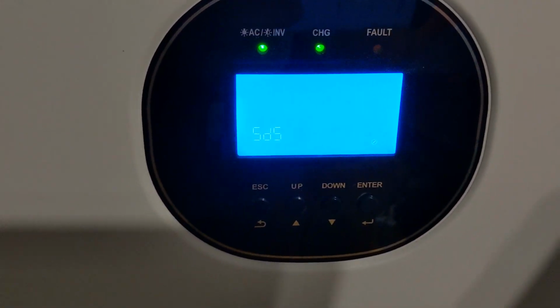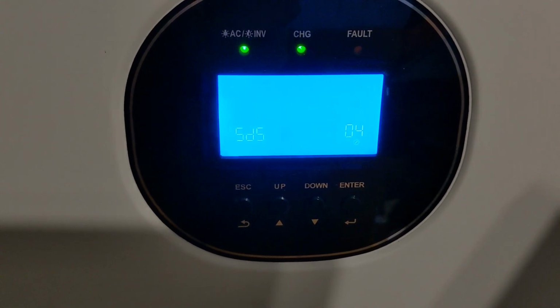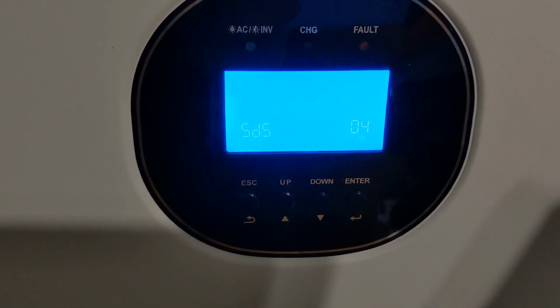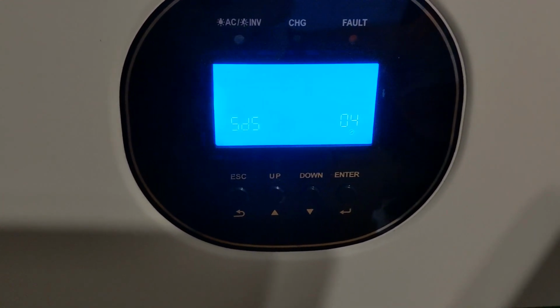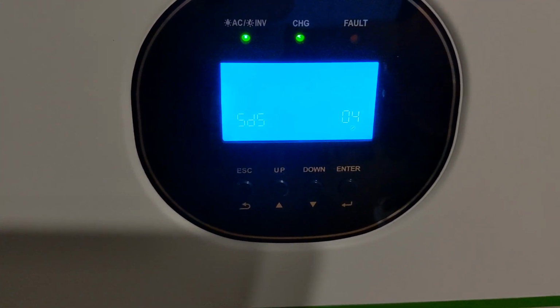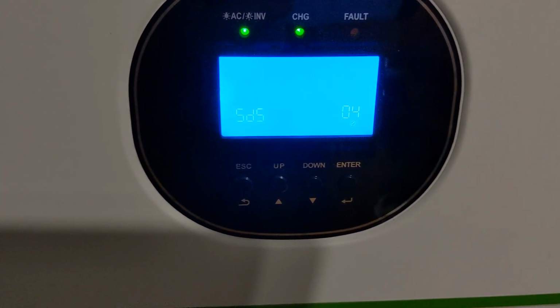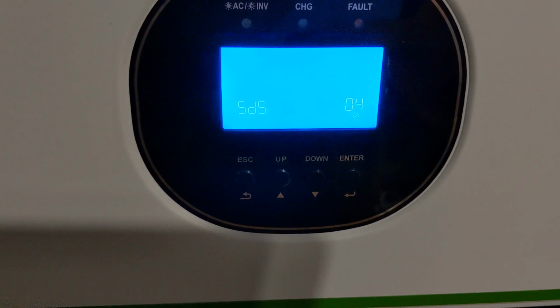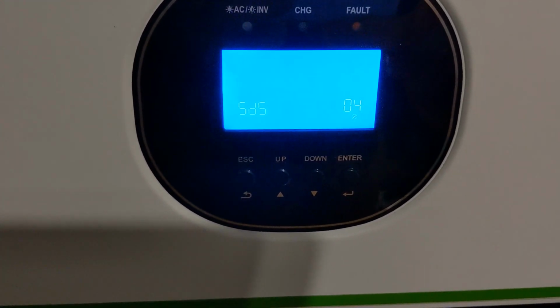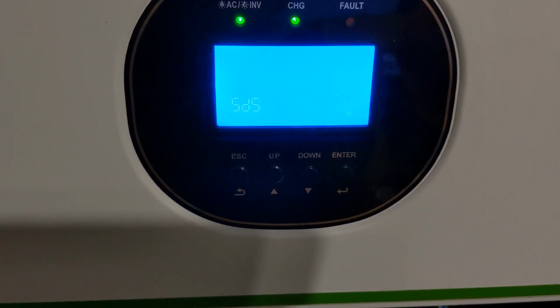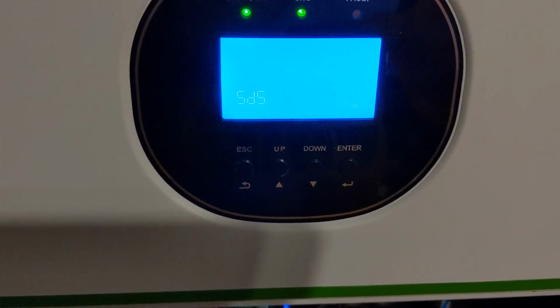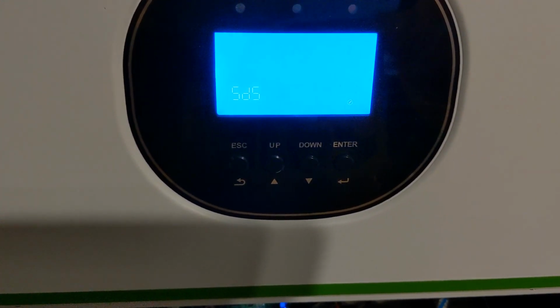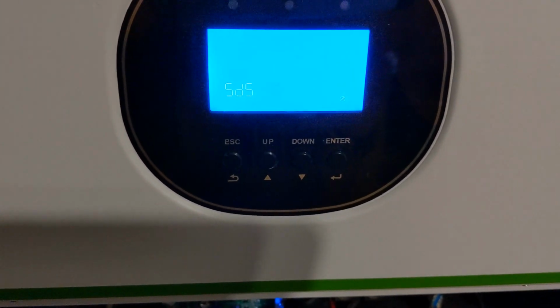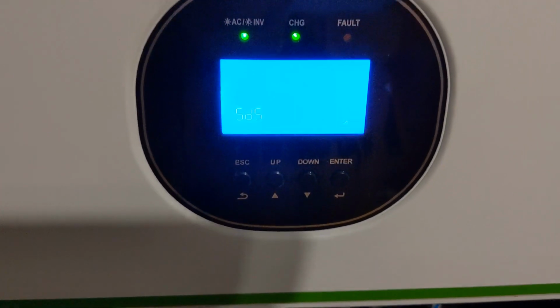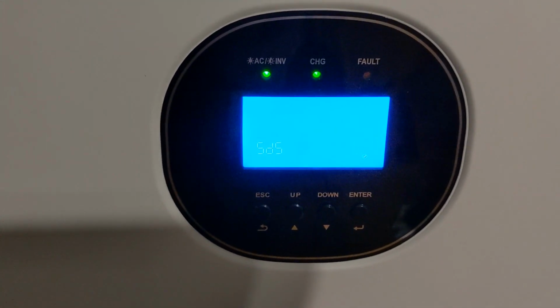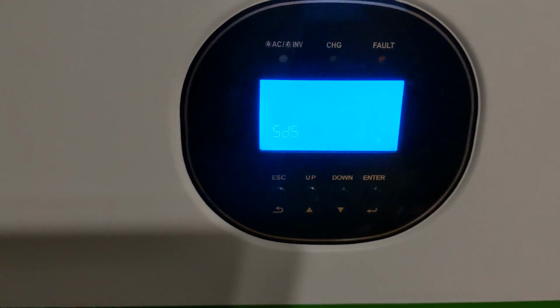So this mode is called SDS. This is the saving mode disable. Basically what this allows it to do is, you turn this mode on. If the load on the unit drops below a minimum amount, then it'll stop. It'll basically shut the inverters off, and then every so often it polls to check to see if there's enough load to turn the inverters on. Unless you're using this in an application where that would fit. Again, I've never had the need to use that mode.